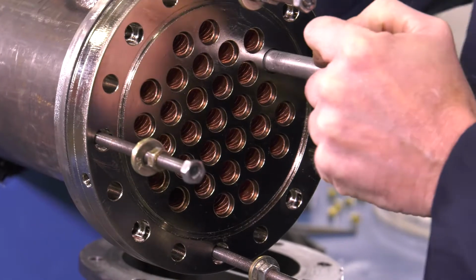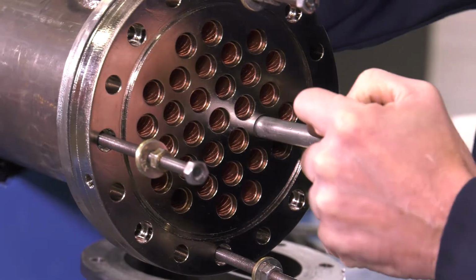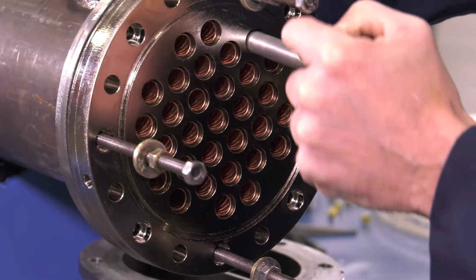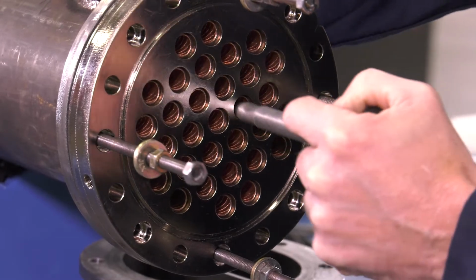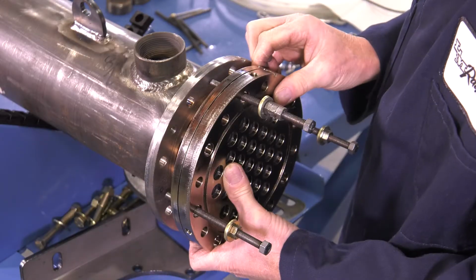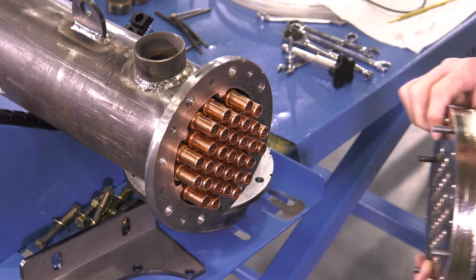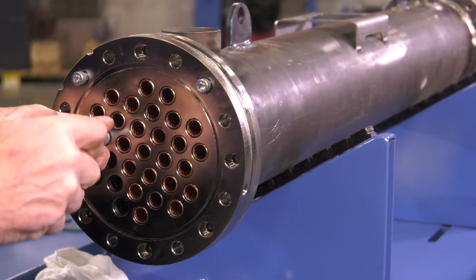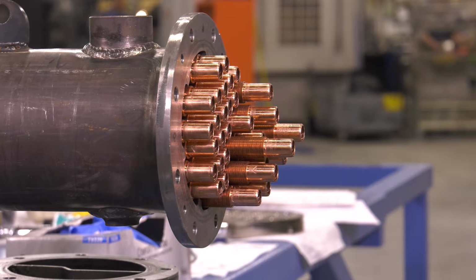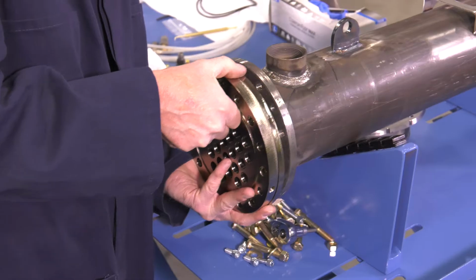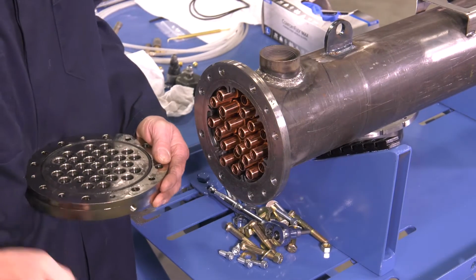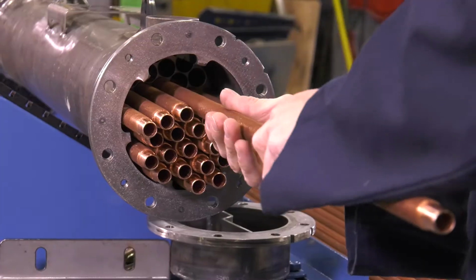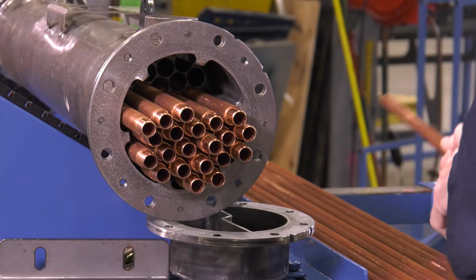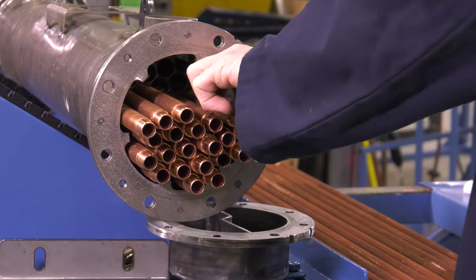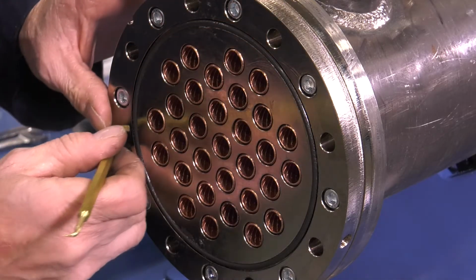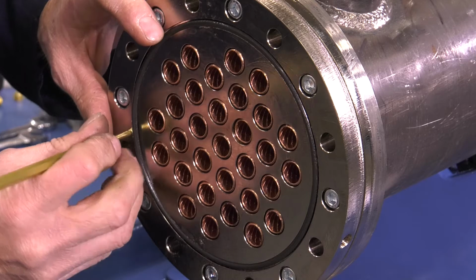If tubes stay attached to the header, use the tube driver tool to push them out of their seals and back into the baffle assembly. Remove the header from the shell flange. Push the tubes from the remaining header using the tube driver tool. Remove the second header in the same manner as the first. Remove the tubes one at a time and place on table or cart. Carefully remove and clean the O-ring seal off the header plates.